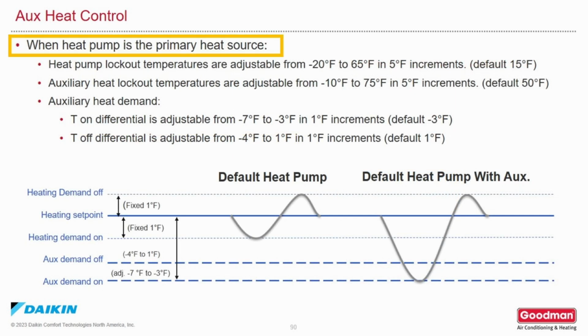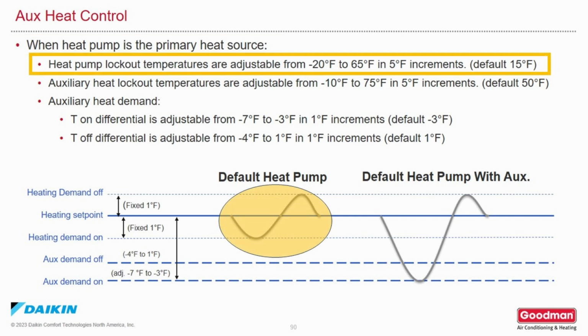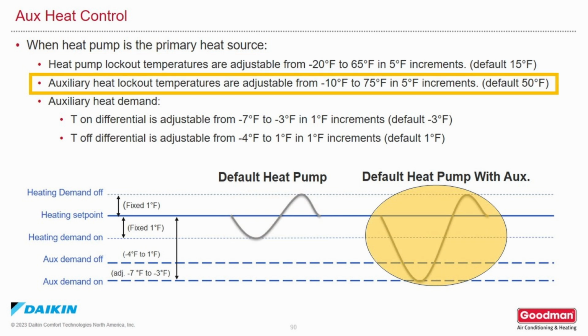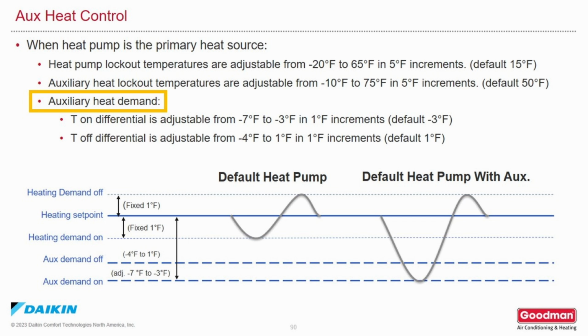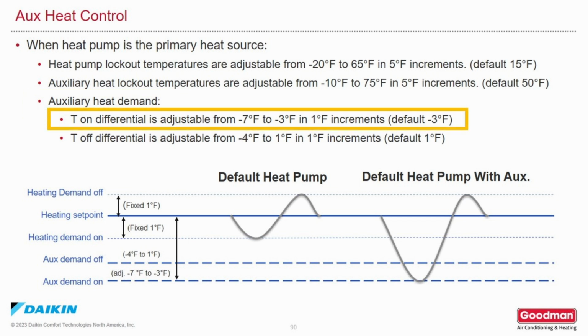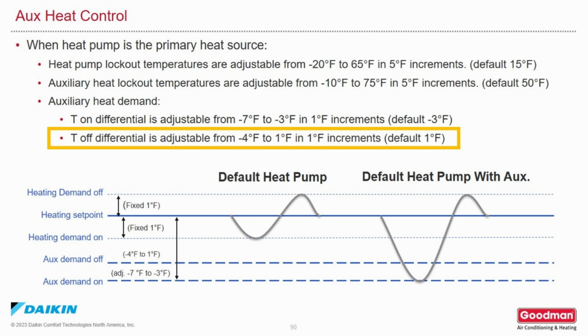When a heat pump is your primary heat source, heat pump lockout temperatures are adjustable from minus 20 degrees Fahrenheit to 65 degrees Fahrenheit in 5-degree increments. Default is 15 degrees Fahrenheit. Auxiliary heat lockout temperatures are adjustable from minus 10 degrees to 75 degrees Fahrenheit in 5-degree increments. Default is 50. Auxiliary heat demand T-on differential is adjustable from minus 7 to minus 3 degrees Fahrenheit in 1-degree increments. Default is minus 3. T-off differential is adjustable from minus 4 to 1 degree Fahrenheit in 1 degree Fahrenheit increments. Default is 1 degree.